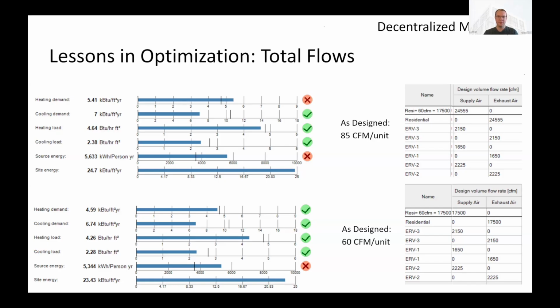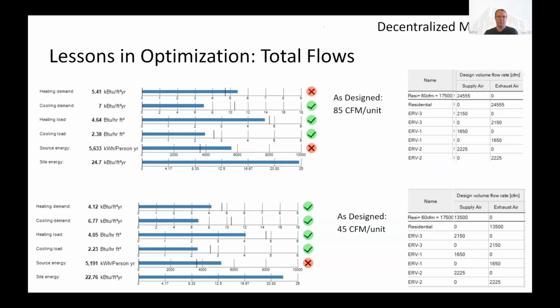The thing is, 60 CFM is sort of a compromise, because if we were really looking at the absolute minimum that we could achieve for the project, it would be 45 CFM, 20 for the bathroom and 25 for the kitchen, per that Energy Star exception in footnote 76 that I showed near the beginning of the presentation. And if we were to do that, it reduces total airflow even further. And now we're looking at 450 kilowatt hours a person per difference, and a really quite significant heating demand and heating load difference.